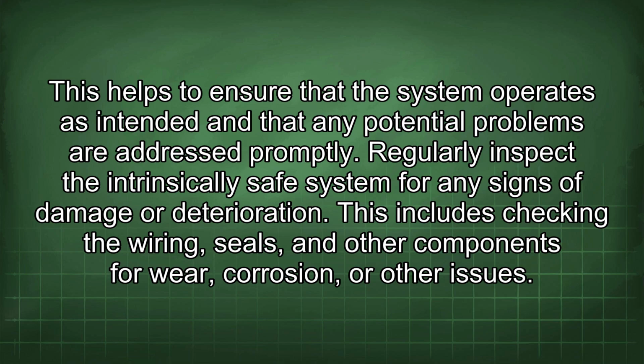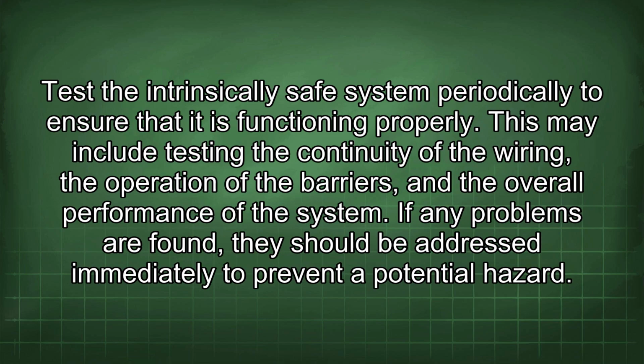Regularly inspect the intrinsically safe system for any signs of damage or deterioration. This includes checking the wiring, seals, and other components for wear, corrosion, or other issues. Test the intrinsically safe system periodically to ensure that it is functioning properly. This may include testing the continuity of the wiring, the operation of the barriers, and the overall performance of the system. If any problems are found, they should be addressed immediately to prevent a potential hazard.